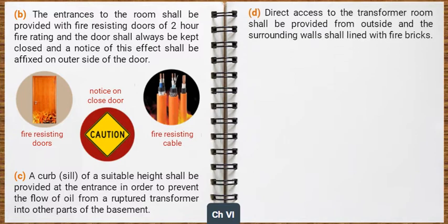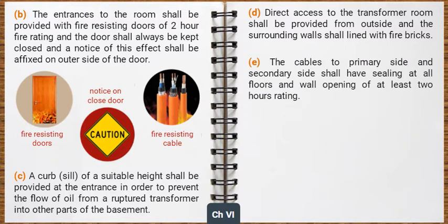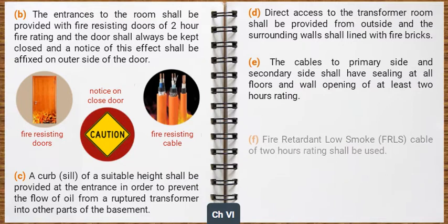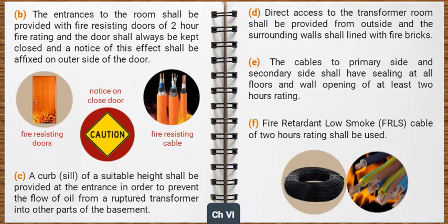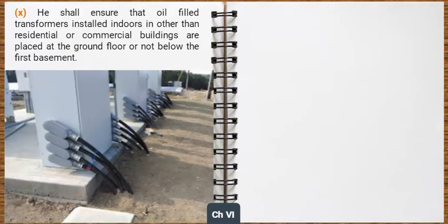Direct access to the transformer room shall be provided from outside, and the surrounding walls shall be lined with fire bricks. The cables to primary side and secondary side shall have sealing at all floors and wall openings of at least 2 hours rating. Fire retardant low smoke (FRLS) cable of 2 hours rating shall be used. He shall ensure that oil-filled transformers installed indoors in other than residential or commercial buildings are placed at the ground floor or not below the first basement.